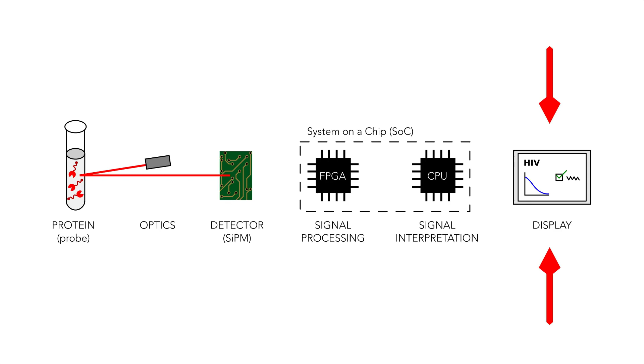So to obtain an HIV viral load count from a blood sample, our system takes advantage of a fluorescent probe that we designed to tag itself to the GP120 protein that presents itself on the surface of the HIV virus. And so within our optical setup, the sample is then interrogated by a laser beam, which excites the probe at a specific wavelength and emits photons that correspond to the amount of virus particles that are present. And so the photons are detected on a silicon photomultiplier, or SiPM, and the signal is processed and interpreted on an FPGA and CPU unit that is on a small chip. This is processed and displayed on a small LCD screen, and the readout is in the form of a numerical value of viruses per milliliter and a graphical representation of the viral count. And so this can be used in clinical decision making.